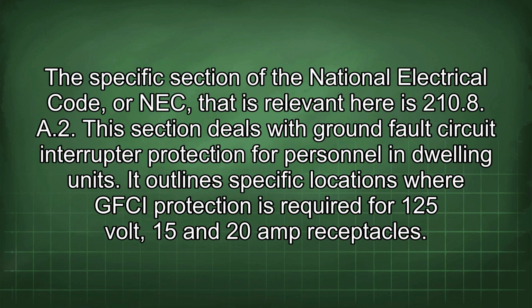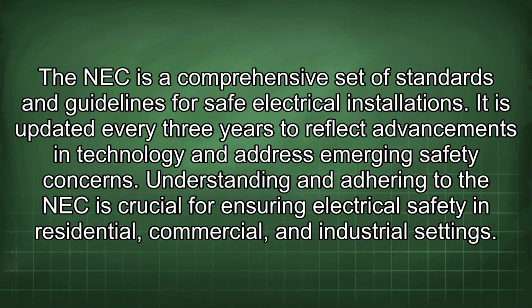The specific section of the National Electrical Code, or NEC, that is relevant here is 210.8.A.2. This section deals with ground fault circuit interrupter protection for personnel in dwelling units. It outlines specific locations where GFCI protection is required for 125 volt, 15 and 20 amp receptacles. The NEC is a comprehensive set of standards and guidelines for safe electrical installations. It is updated every 3 years to reflect advancements in technology and address emerging safety concerns. Understanding and adhering to the NEC is crucial for ensuring electrical safety in residential, commercial, and industrial settings.